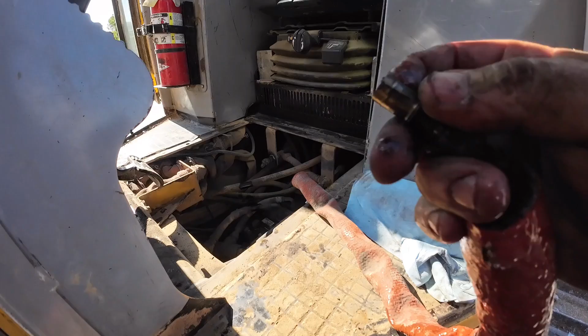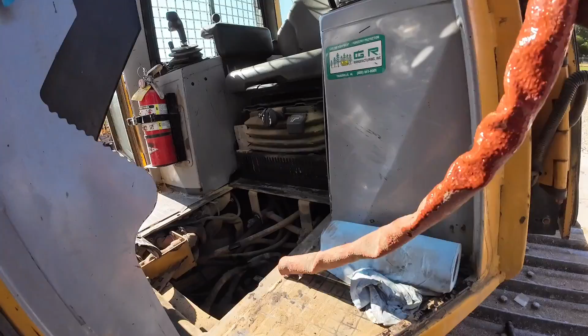Alright, got the new one in there. Checking the old one out here. If you see marks on the ends of these things, that means something's usually coming apart inside the pump or drive motor. Won't see nothing on that one. These things are kind of famous for going bad.